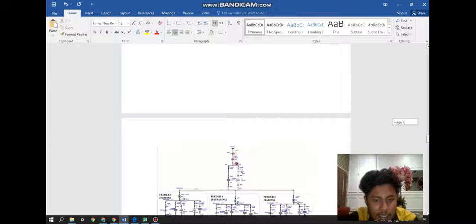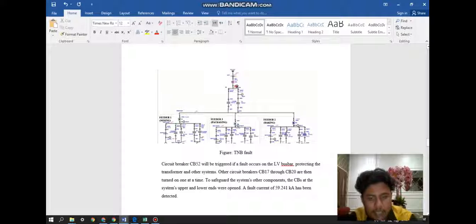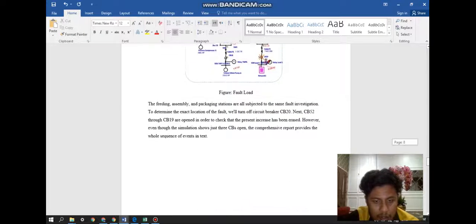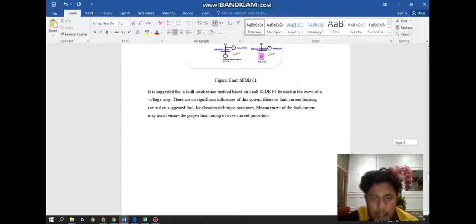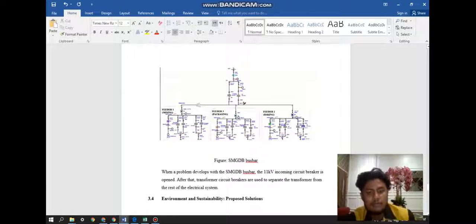Okay, so I proceed to simulation result and discussion. So this is our simulation from the ETAP. So there is here a TNB fault. Circuit breaker CB52 will be triggered if a fault occurs in the LV bus bar, protecting the transformer and other systems. Other circuit breakers CB17 through CB20 are then turned on one at a time to safeguard the system's other components. The CBs at the system's upper and lower ends were open. So a fault current of 59.241 kA has been detected. Okay, this is for the fault load for SPDB F1 and for the SMGDB bus bar. So when a problem develops with the SMGDB bus bar, the 11 kV incoming circuit breaker is open. After that, the transformer circuit breakers are used to separate the transformer from the rest of the electrical system.